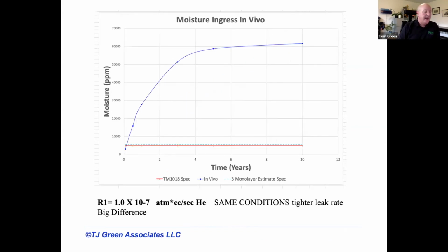Okay. Now, if we go to a higher leak rate, if we change that leak rate just one order of magnitude, you can see in no time at all, I'm up close to that 60,000 point. And that's where you're going to saturate. You're not going to ever get more than 60,000 in there, because once the internal atmosphere comes to equilibrium with the body, I think it settles out about 60,000 parts per million. You can't get any more in there.